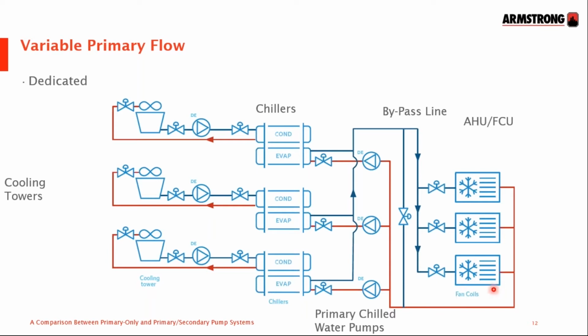The thing to note here on a variable primary is that at periods of very low demand and consequently low flow, the controls will be set to open up this valve here in the bypass line. This bypass line valve is normally shut, but it will open when the flow rate drops to a very low number below the minimum flow stated for a chiller, where the chiller would otherwise go into a low temperature cutout. So you need to have a flow meter here in the mechanical room, connected to the building management system, ready to open up this valve at the drop of a hat, thus providing minimum flow through the chillers and preventing low temperature cutout.